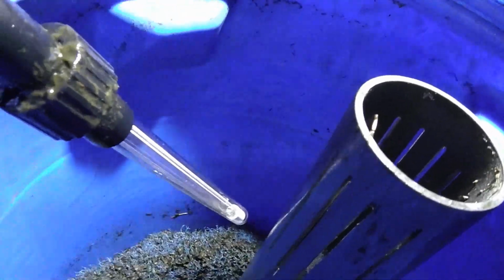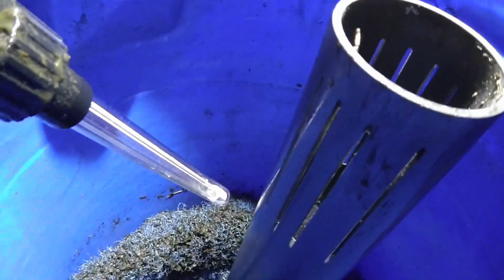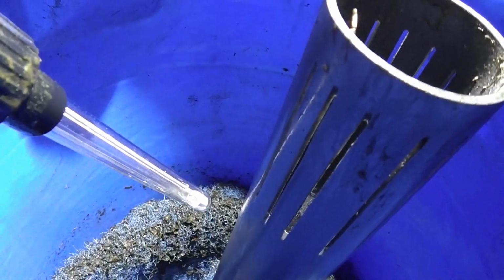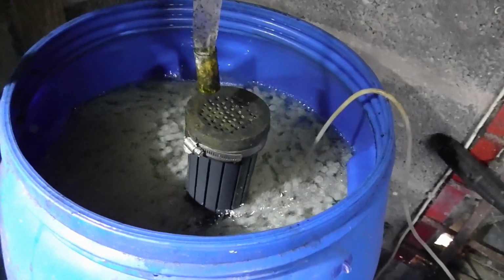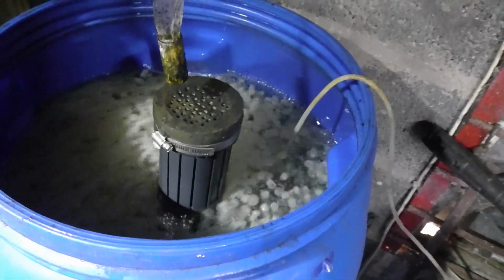So that's the submersible UV. It's an amalgam lamp, so it's very powerful, and it actually kills all the bacteria, which is great for when it comes in. The main bacteria filter is based on K1, which they're based in a barrel just after that vortex, and that's a moving bed, so there's air just moving the K1 all the way around.